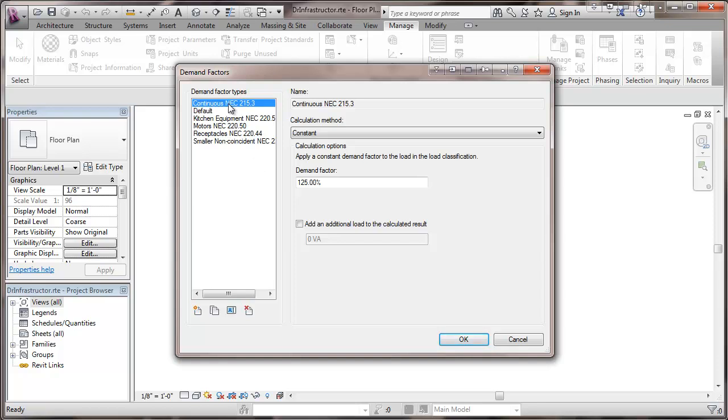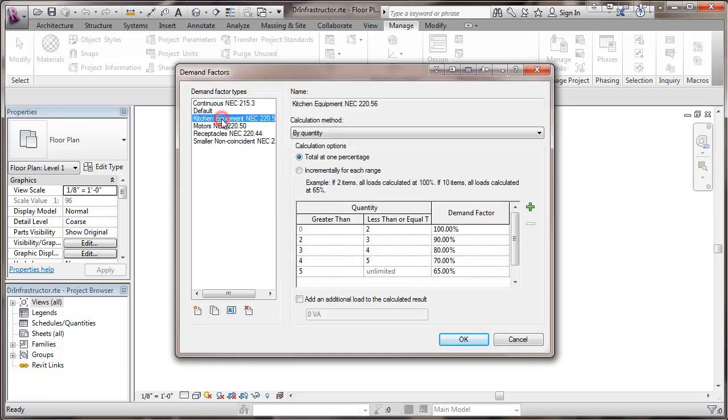Here we have our continuous loads shown as a constant calculation method and 125 percent demand factor. One item that's been added is kitchen equipment and kitchen equipment is a demonstration of a calculation by quantity and it's a total of one percentage.